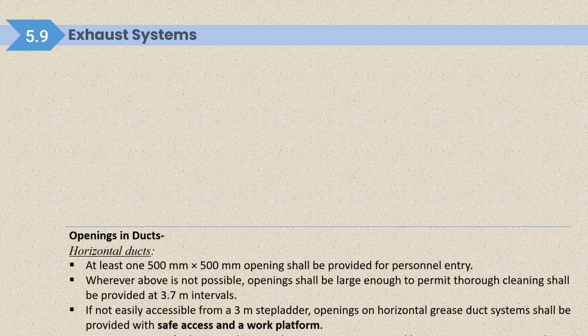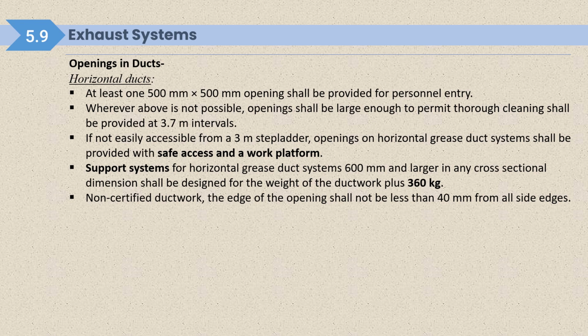Exhaust system openings in ducts: at least one 500 mm by 500 mm opening shall be provided for personnel entry. We are talking about horizontal duct. Wherever this is not possible, openings large enough to permit thorough cleaning shall be provided at 3.7 meter intervals. So we need to provide a 500 mm by 500 mm opening at an interval of 3.7 meters.